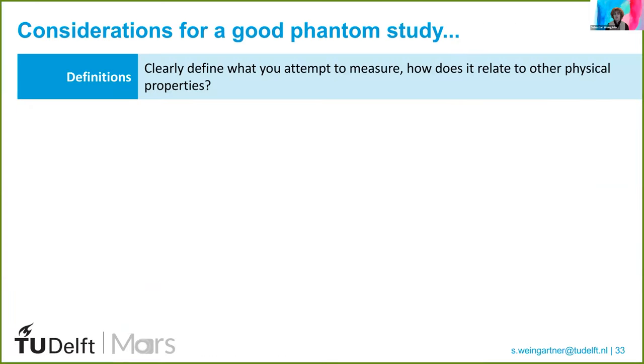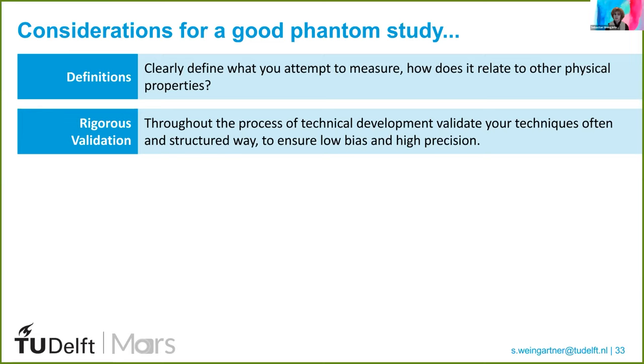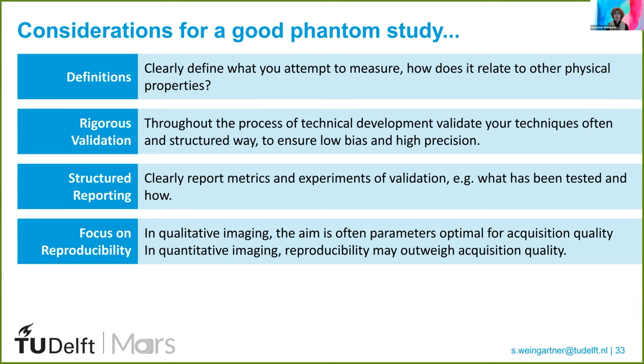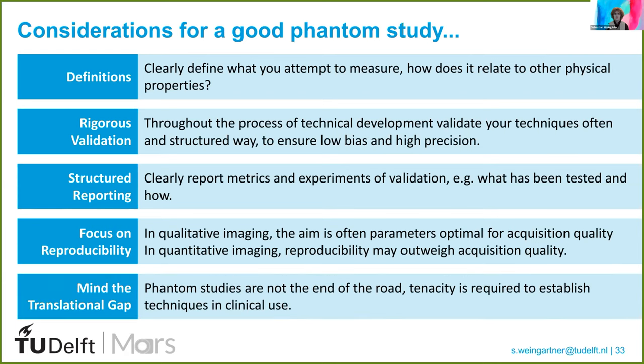To sum up, I want to conclude with a few recommendations on how to do a good phantom study. First, clearly define what you attempt to measure. Think about how this measurement is related to other physical properties and how it can best be ascertained as a reference value. Throughout the entire process, perform rigorous validation at every step, repeatedly assessing bias and precision to ensure no step compromises your measurement quality. Be very structured in your reporting and clearly tell the reader what has been tested, what has been constant, and what has remained the same. In quantitative imaging, the focus may be put on reproducibility rather than image quality. Keep in mind that phantom studies are not the end of the road — a lot of tenacity and work is needed to bring it all the way through translation.